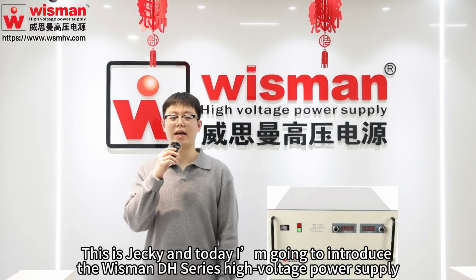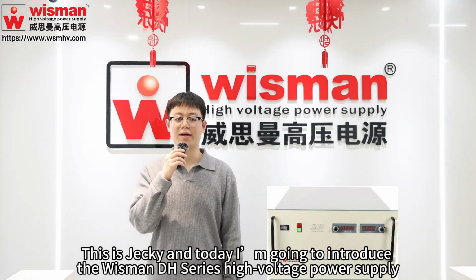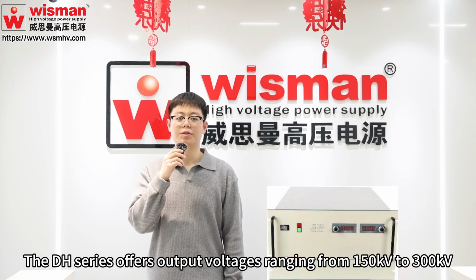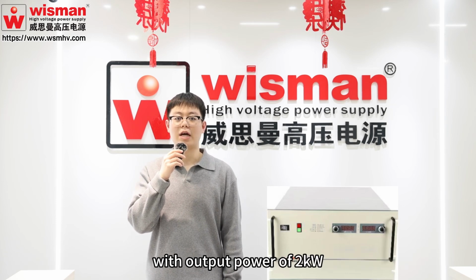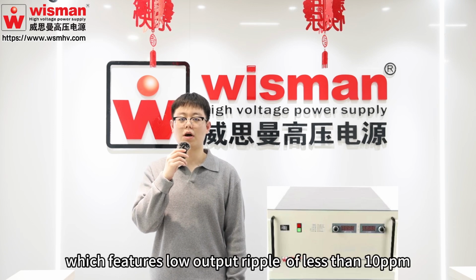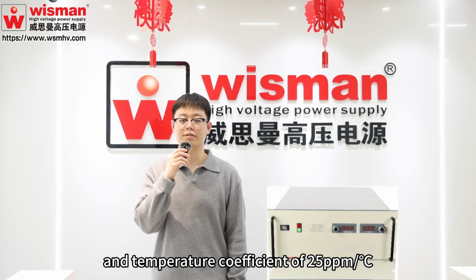This is Jackie and today I'm going to introduce the Wisman DH series high voltage power supply. The DH series offers output voltage ranging from 150 kV to 300 kV with output power of 2 kW, which features low output ripple of less than 10 ppm and a temperature coefficient of 25 ppm per degree Celsius.